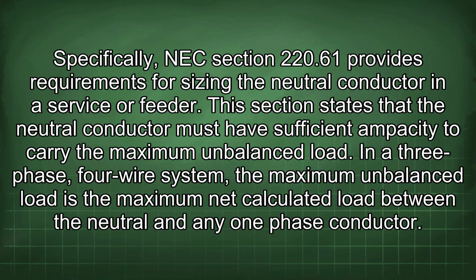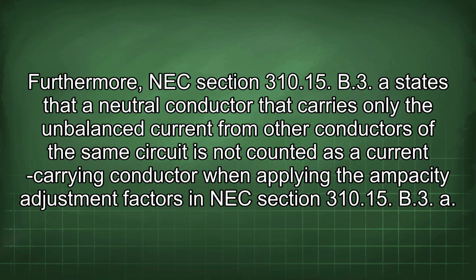Specifically, NEC section 220.61 provides requirements for sizing the neutral conductor in a service or feeder. This section states that the neutral conductor must have sufficient ampacity to carry the maximum unbalanced load. In a three-phase, four-wire system, the maximum unbalanced load is the maximum net calculated load between the neutral and any one-phase conductor. Furthermore, NEC section 310.15(B)(3)(a) states that a neutral conductor that carries only the unbalanced current from other conductors of the same circuit is not counted as a current-carrying conductor when applying the ampacity adjustment factors in NEC section 310.15(B)(3)(a).